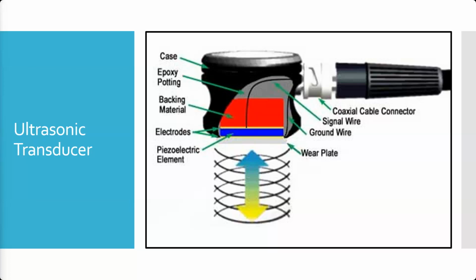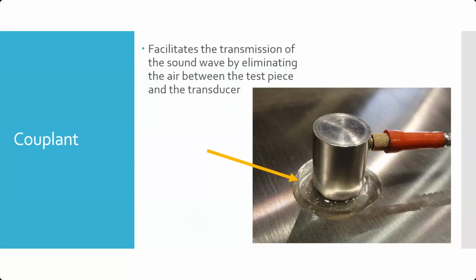Now, every time we have a material interface, we get a reflection of sound. That also is going to attenuate the sound. It's going to reduce the amplitude of the ultrasonic wave. So what we're going to use is something called an acoustic couplant, or we just refer to it as a couplant, to acoustically bind our probe, our transceiver, to the test piece, to the material. It eliminates any air. Air is a good insulator of sound, so the couplant fills in. You're always going to have that face, that wear plate, and the face of our part. You can even see there's grain structure on this part, it is not perfectly flat.